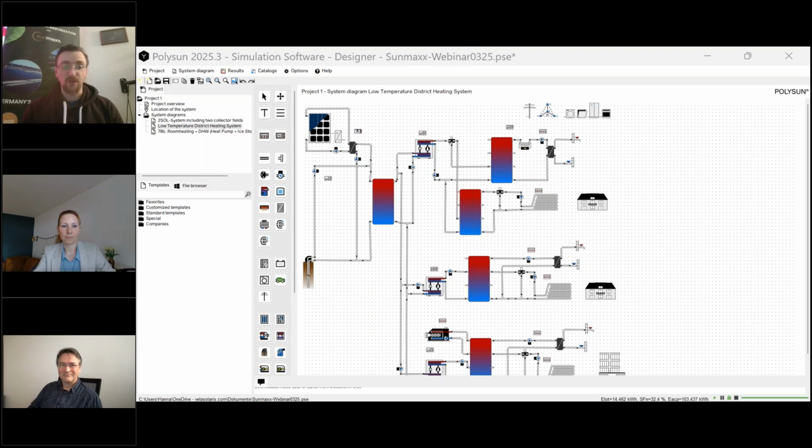And even for the brine heat pump, it doesn't matter if we deliver minus 10 degrees or if we deliver 25 degrees. Of course, the difference is the efficiency of the brine heat pump. But even with minus 10, minus 15 degrees, with the correct brine heat pump on your side, it's never a problem for the space heating or for the domestic hot water. Thank you very much.